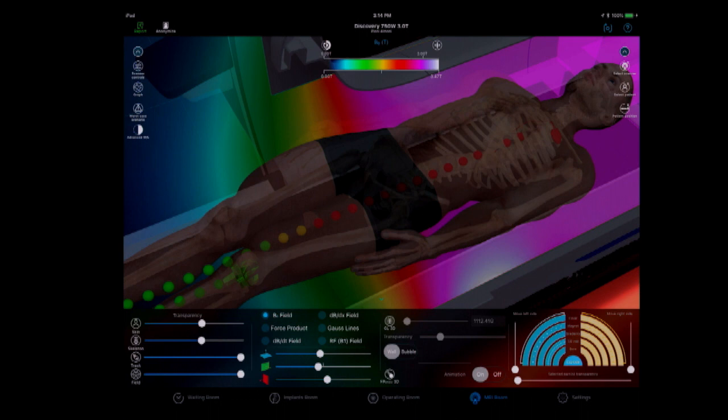So at these positions in space, wherever it was, there was not an issue; yellow was approaching, and in no time at all, in no space at all, in this example, that pacemaker on that MR scanner exceeded its safety for, what energy are we looking at, B0? It had exceeded it right there. Does everyone understand what it's trying to show?